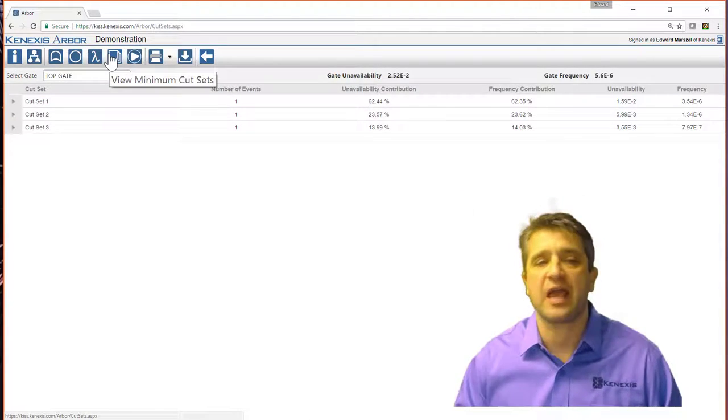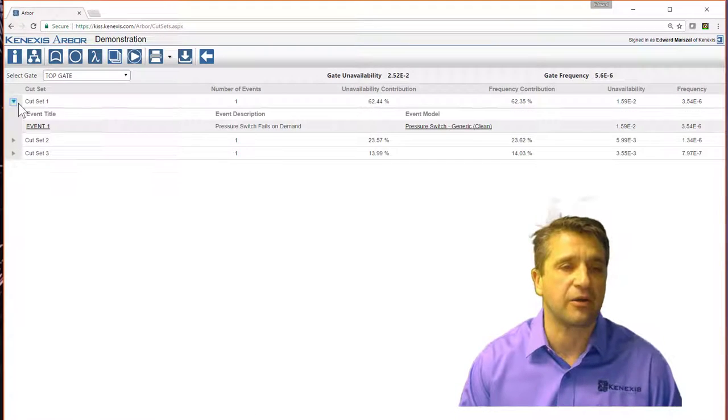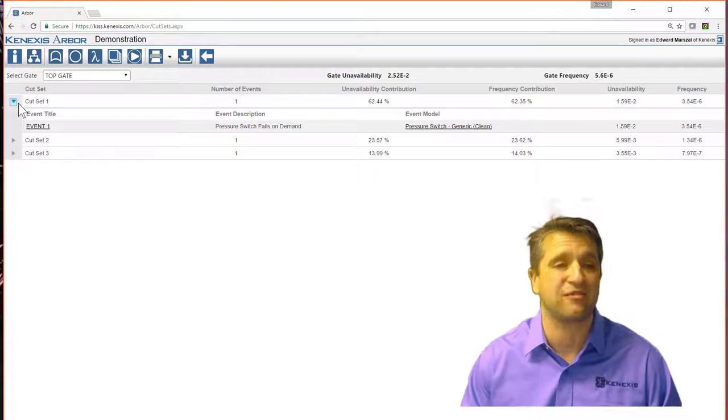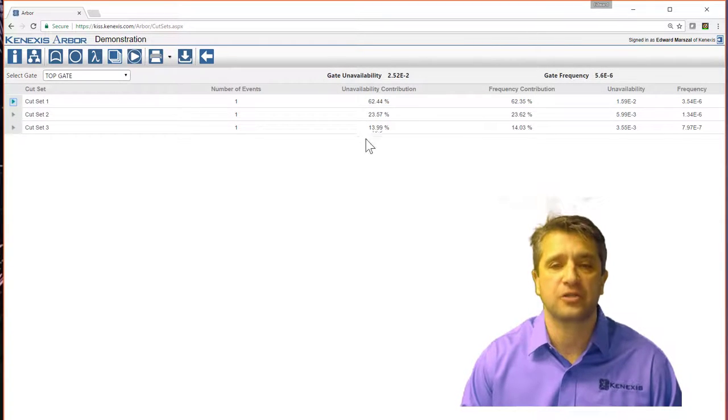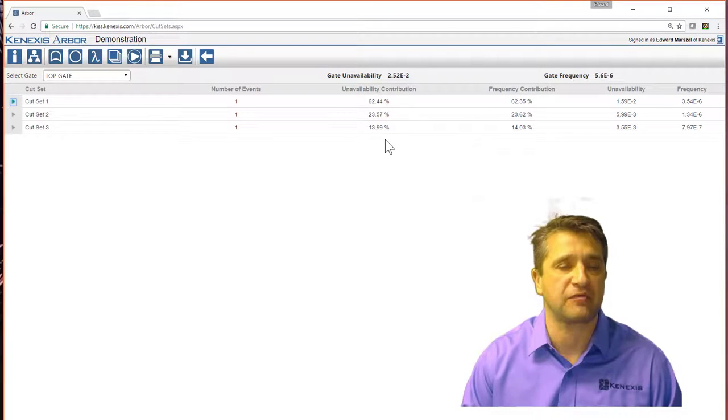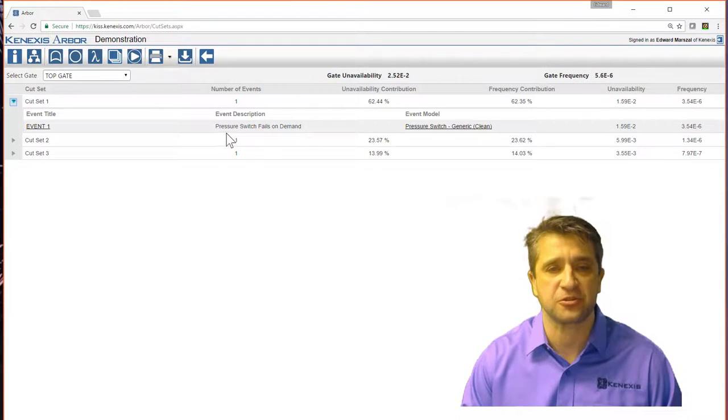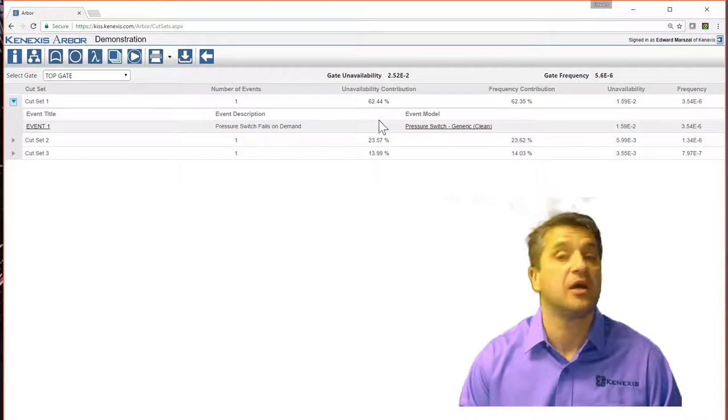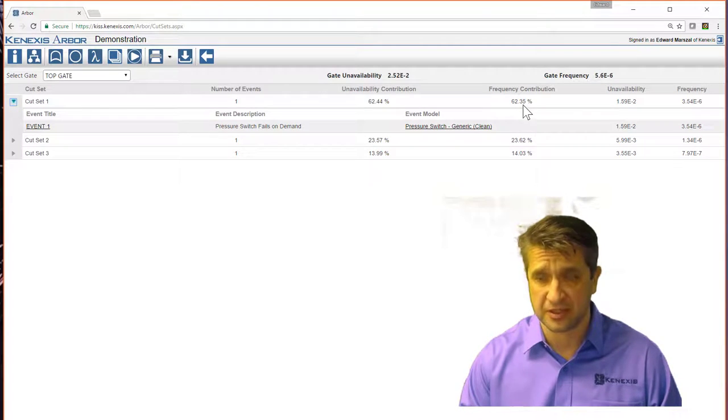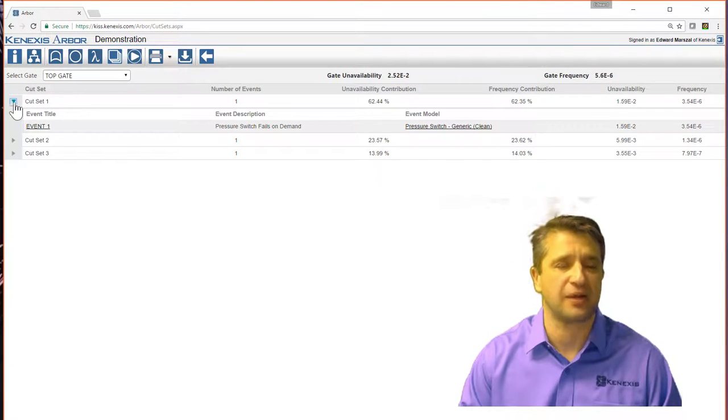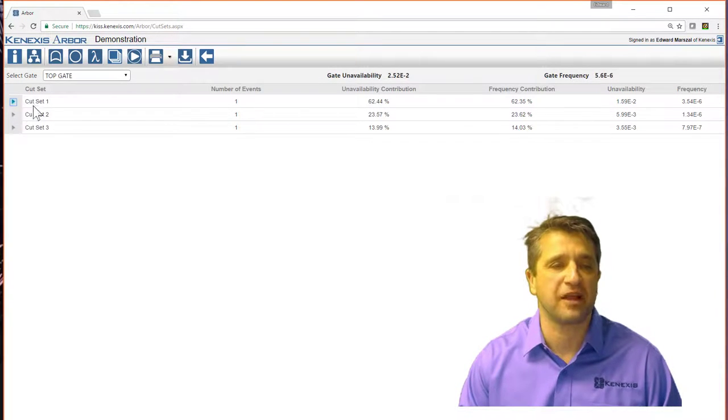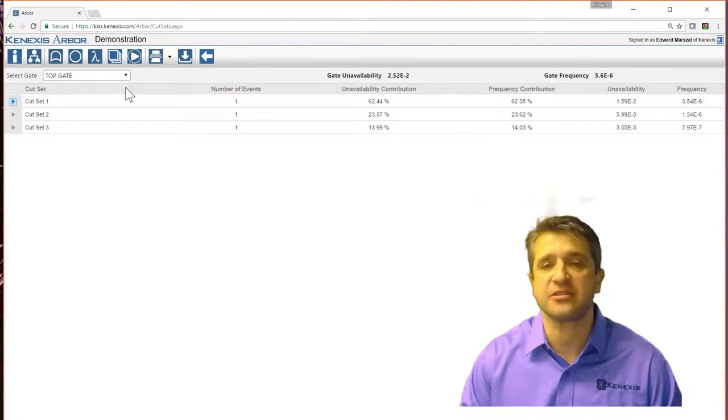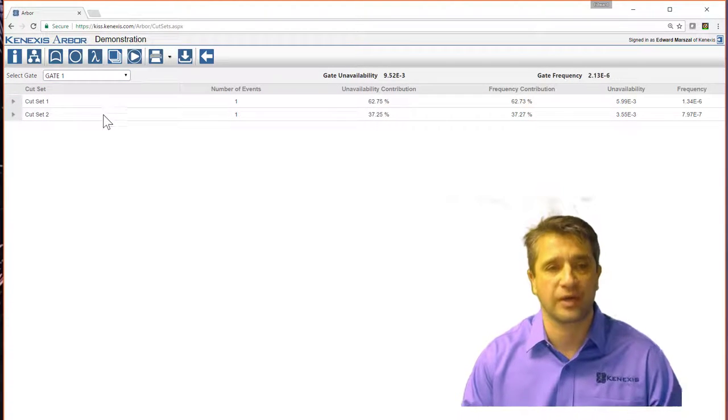We also have a minimal cut set view that's going to allow you to look at all the cut sets that were generated in the fault tree analysis calculation, what their contribution is to the overall PFD. So cut set number one, which is the pressure switch failing on demand, actually contributes 62% of the unavailability and 62% of the frequency contribution. So that's your bad actor. So full comprehensive cut set analysis capabilities.